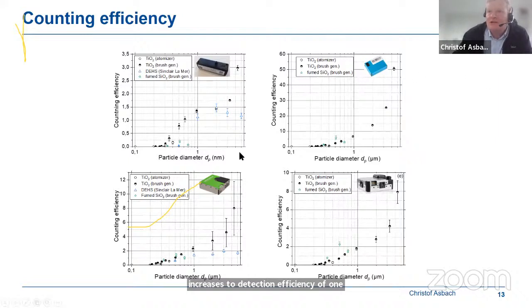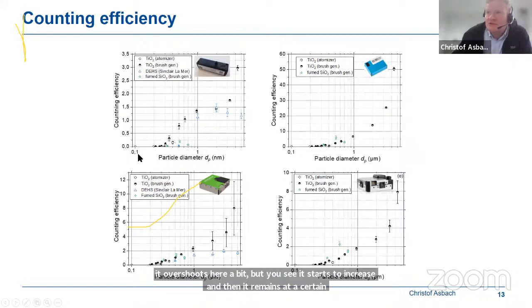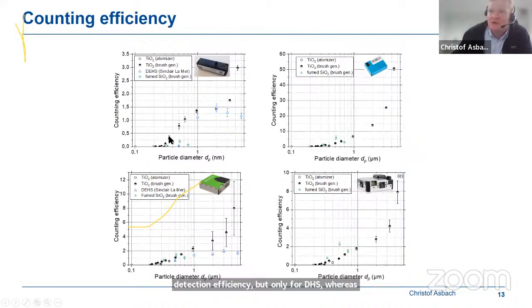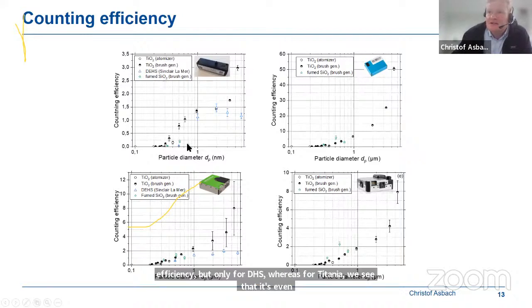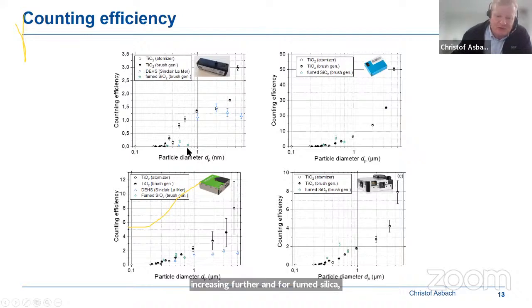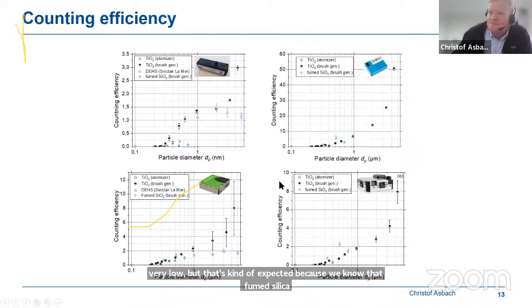In fact, the only device that has a detection efficiency somewhat similar to what we would expect is the AlphaSense spectrometer, although it overshoots here a bit. You see it starts to increase and then remains at a certain detection efficiency, but only for DEHS, whereas for titania we see that it's even increasing further. And for fumed silica, it's actually very low, but that's kind of expected because we know that fumed silica is just poorly detected by optical measurement devices.